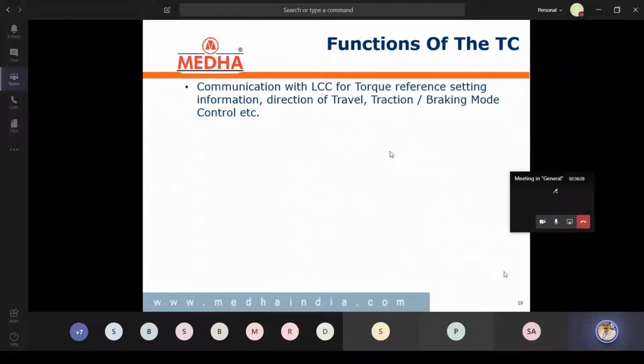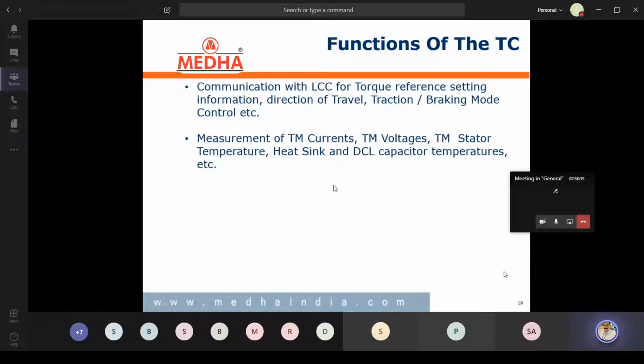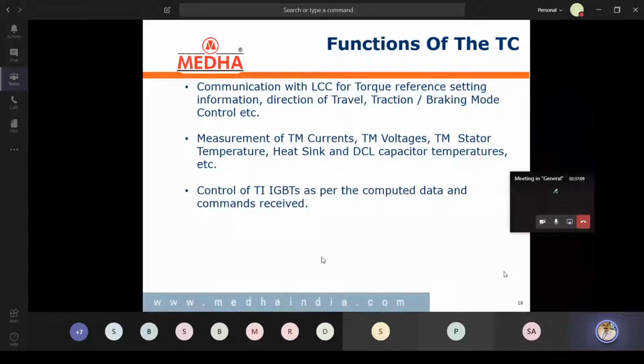So the primary function of the traction computer is to receive the data from LCC, and then locally this computer monitors all the safety parameters, whether I can give full torque as per LCC requirement or I need to derate the power or limit the power based on the local conditions. Like that, all the 6 individual traction computers monitor their local parameters, and accordingly decide the torque. So for that purpose, it monitors all the TM currents, TM voltages, stator temperature, heatsink temperatures of the phase module, and DC link capacitor temperatures. Everything will be monitored by local computers, and accordingly it further controls the traction inverter IGBTs as per the computed data and commands received.